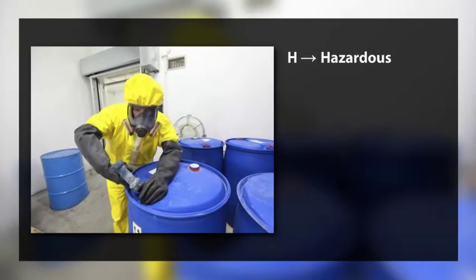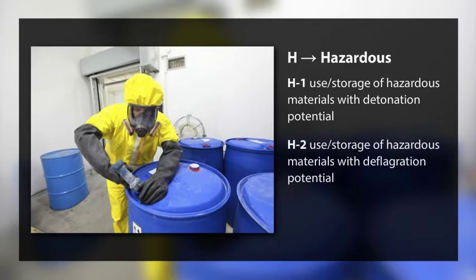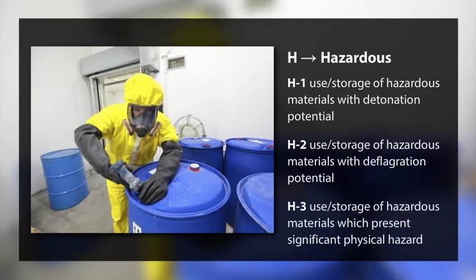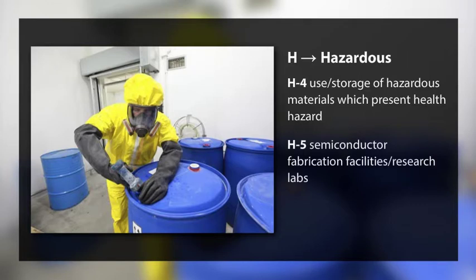Hazardous subgroups: H-1 — use or storage of hazardous materials with a detonation potential; H-2 — use or storage of hazardous materials with a deflagration potential; H-3 — use or storage of hazardous materials which present a significant physical hazard; H-4 — use or storage of hazardous materials which present a health hazard; H-5 — semiconductor fabrication facilities or research labs.